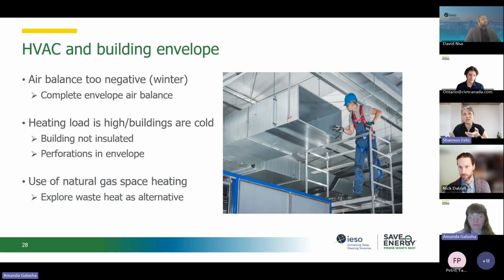To alleviate this, the low-hanging fruit here is to do an envelope air balance in the wintertime, and things like closing holes or gaps in the building. But also perhaps it's as simple as turning off excess exhaust fans in the wintertime, so having a winter and a summer mode for our buildings.